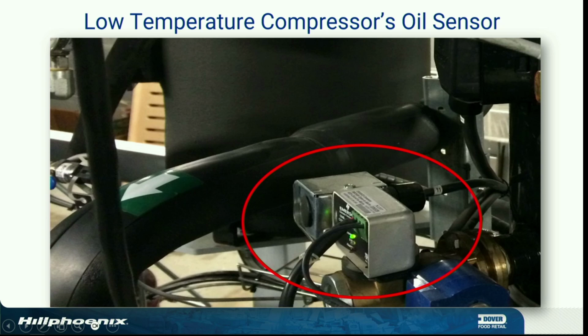So if you do go on a call and got a call at the compressor, you got a compressor oil trip, you get up on a roof and the compressor's running, what happened? Come on, what happened? It filled, it tripped, and then it started on the 2nd to the 4th time because it locks out on the 5th, right? Don't you throw that ball at me. No, that's why I like you have it, throw it down. Oh, yeah, that's a good idea. Next time you don't answer, throw, that's right, throw a ball at it.